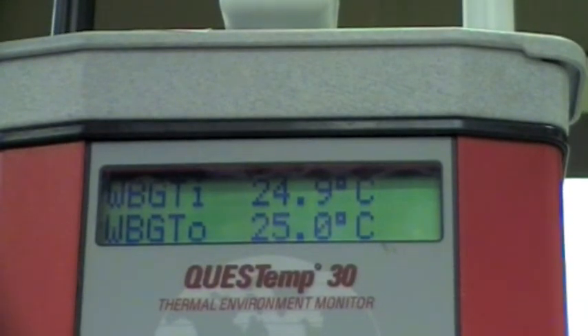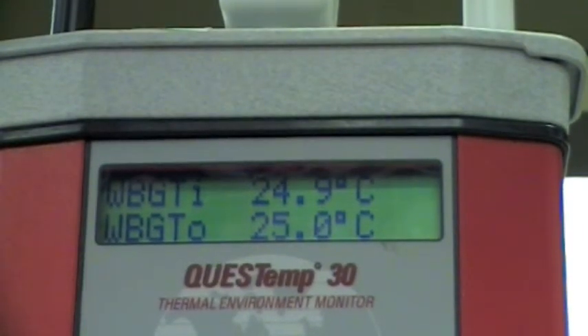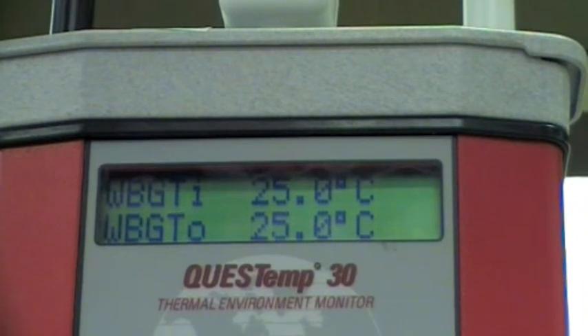On the top is the inside WBGT index. You will note from the module that there is a different formula for calculating WBGT depending on whether it's an indoor environment. In this case in the kitchen it is an indoor environment. So the top indoor value is the one that we should focus on.